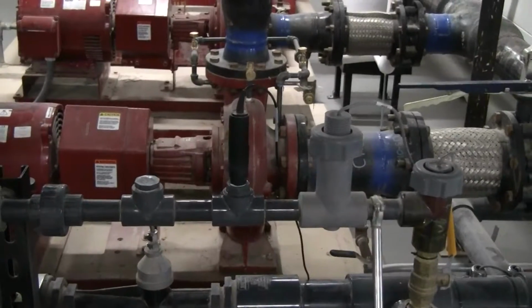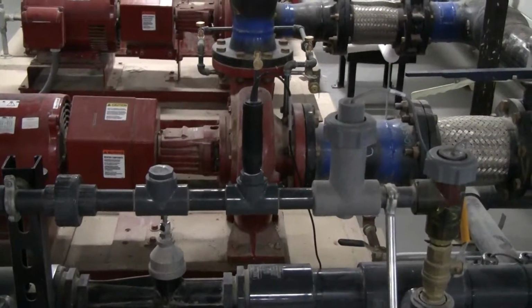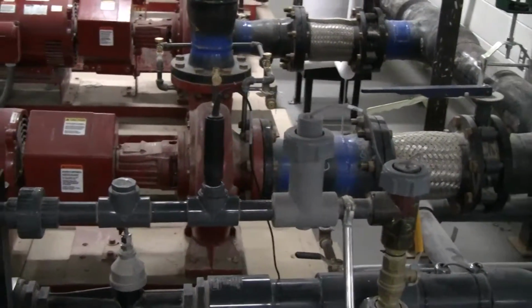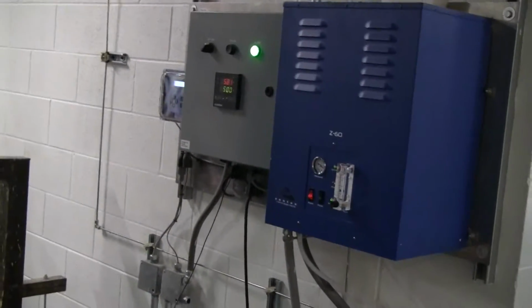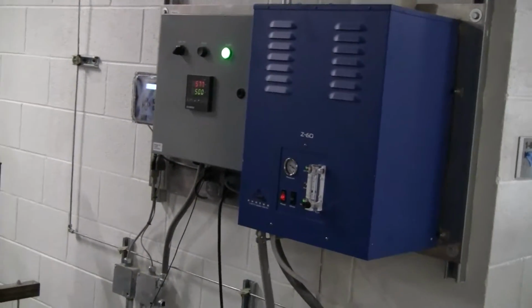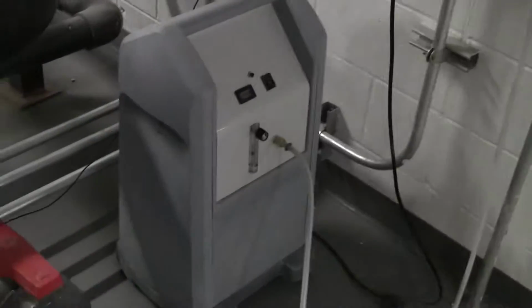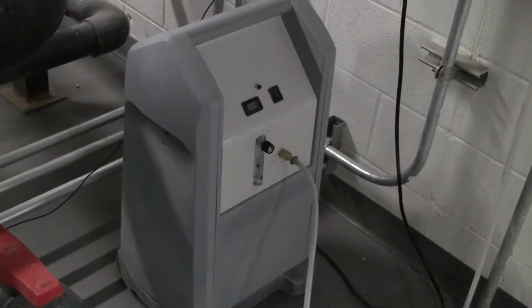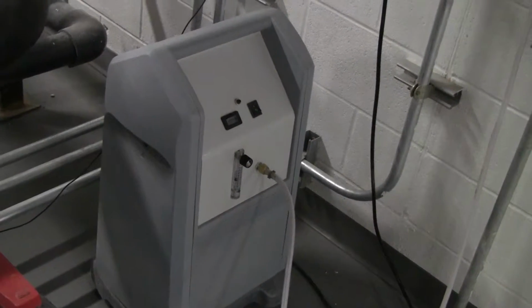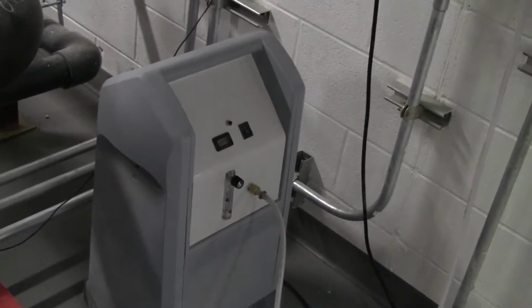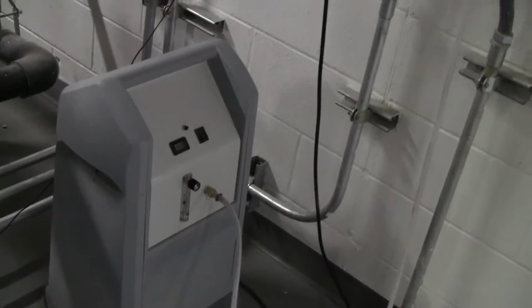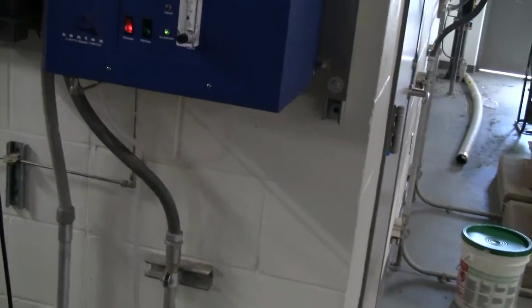And then we have the ORP probe, which is controlling how much ozone we're feeding into the system. It sends a signal over to the controller. The controller tells the generator how much ozone to produce. Over here, we start off with the oxygen generator. This pulls straight air out, strips all the nitrogen out. We have 90 to 95% oxygen feeding into the ozone generator here.